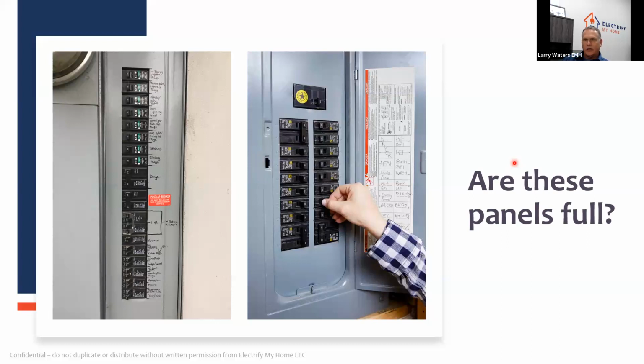We don't know. But just looking at this, the panel here on the left only has really a couple of 240 volt loads, like 3. One of them looks like it might be the AC, and the other one here is a solar. They've got a dryer. And then they've got a bunch of 110 volt light and plug circuit loads. Chances are, if this is a 100 amp panel, this is not a full to capacity panel. This one over here is even better. Like they've got a lot of space in here, but not a lot of space for new breakers. But what can we do to make this work? We could add different circuitry. We'll get up to that in a second.